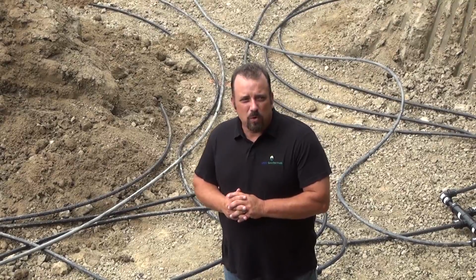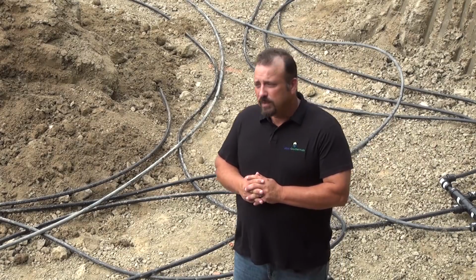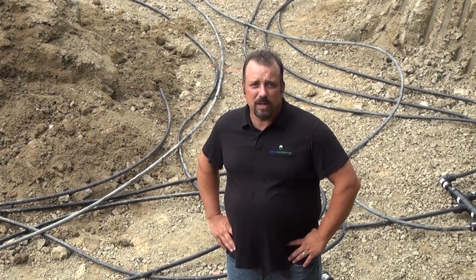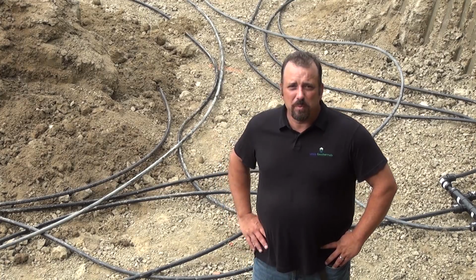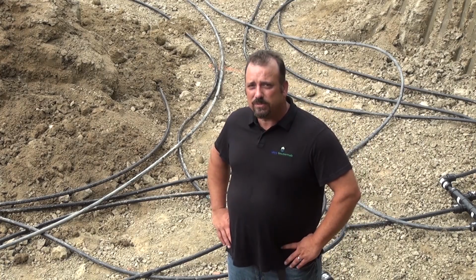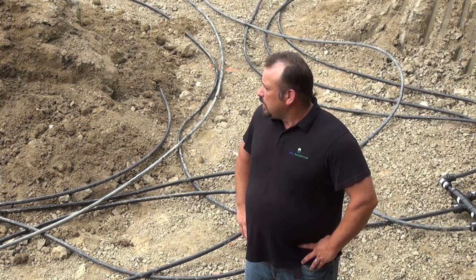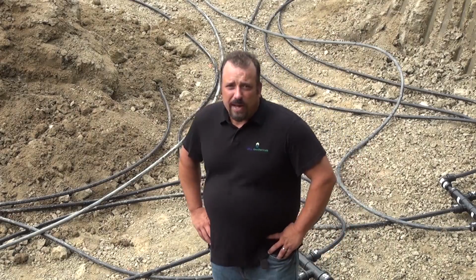Just to give you a general rule of thumb, if you had a home that was fairly well insulated, about 2,500 square feet, you would have roughly a 5-ton system. Now again, that's not the way to properly size a system. It's a basic rule of thumb to give you a rough idea of the thinking process and what needs to happen to do this. So that's about the size of the home that we're at today.